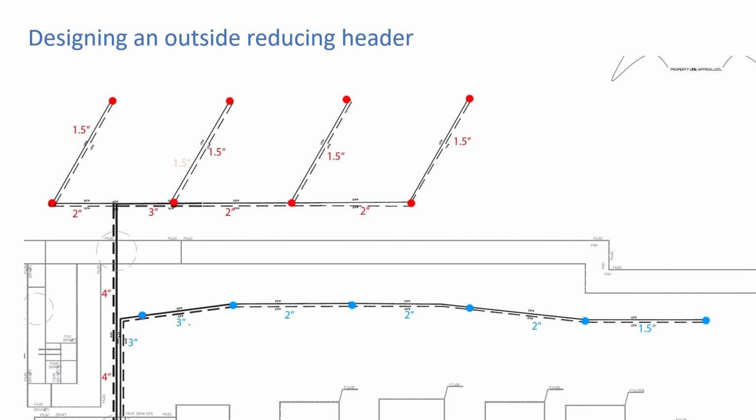So it's interesting, on this large building, we actually have 2 separate loop fields for 2 different portions of the building because we don't want the long runs. We don't want to have centralized everything. We keep it there because otherwise our pumping power goes up. Remember, pumping is the enemy of efficiency. That's what we're trying to do.